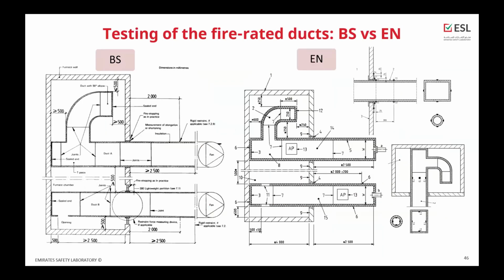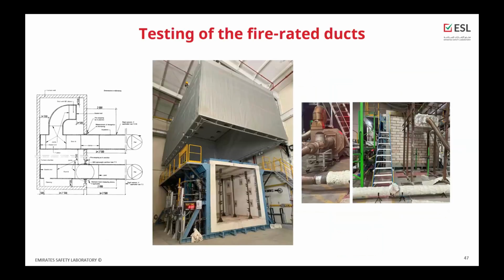The construction of the duct for the testing is quite similar. However, as I said before, there is a difference between the size of duct A and its branch, plus EN is more precise in terms of the insulation criteria, where to put thermocouples. So how are these tests done in our laboratory? We are using this furnace, which is a combo furnace made from two chambers. The length of our chamber is 4.5 meters, but if the client wants to assess a lot of accessories, we can combine those two chambers to get a furnace around 10 meters long.